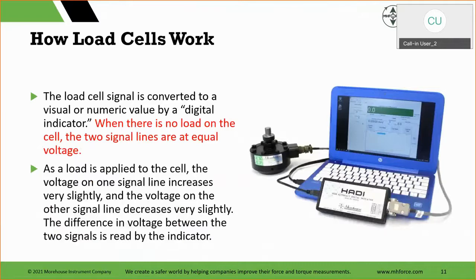Then, how the load cell actually works: the signal is converted to a visual or numeric value by a digital indicator. When there's no load on the load cell, the two signal lines are at equal voltage. As load is applied, the voltage on one signal increases very slightly, and the voltage on the other signal decreases very slightly. We're just measuring this difference with an indicator. Here's a picture of a HADI. This is a high accuracy digital indicator. That's what we chose to name this indicator.